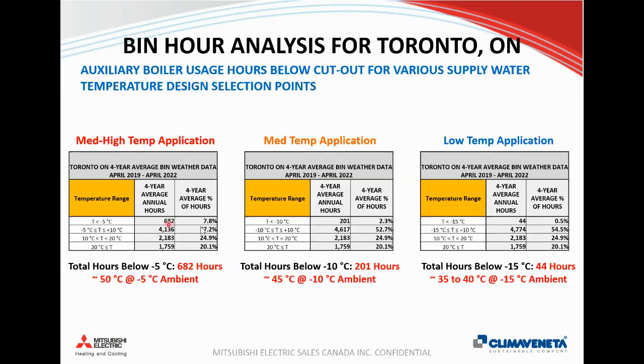And really, we still spend 47% of the year between -5 and +10 for Toronto. And times below -5, we spend about 682 hours. So roughly 3 weeks of the year. But again, that doesn't happen 3 weeks consecutively. Typically it's a cold snap for a day or two, or a few colder temperatures throughout the night that we'll see. So again, it's about using the heat pump where you can get good efficiencies and good supply temperatures within this range, and then auxiliary boiler operating below that. If we're able to design maybe with lower temperature water, 45 degrees, we can achieve that down to -10 typically, and times below -10, we're now talking about 200 hours, or 2.3% of the year.